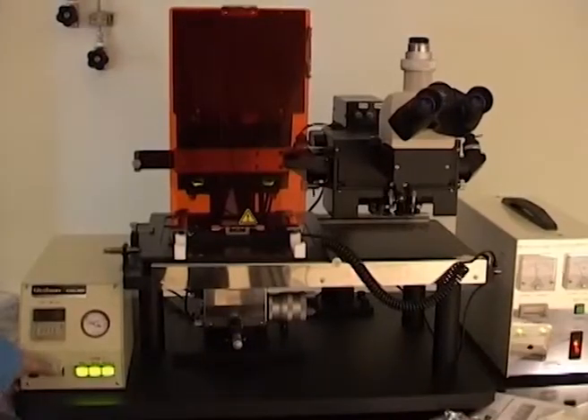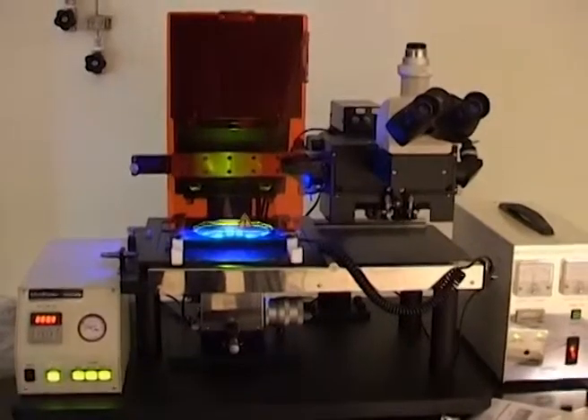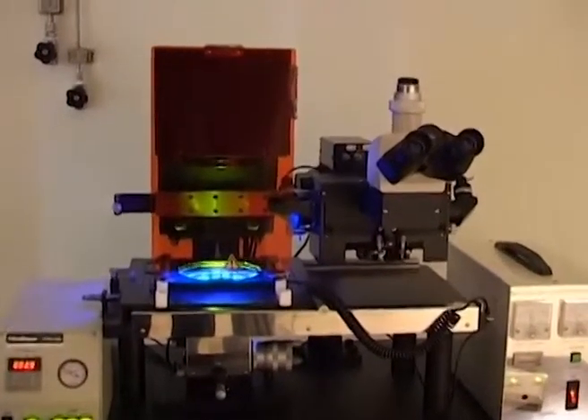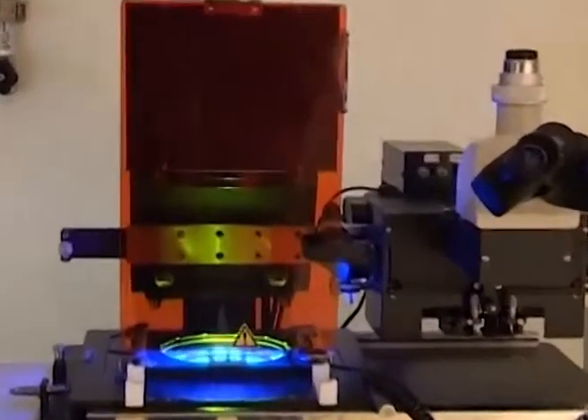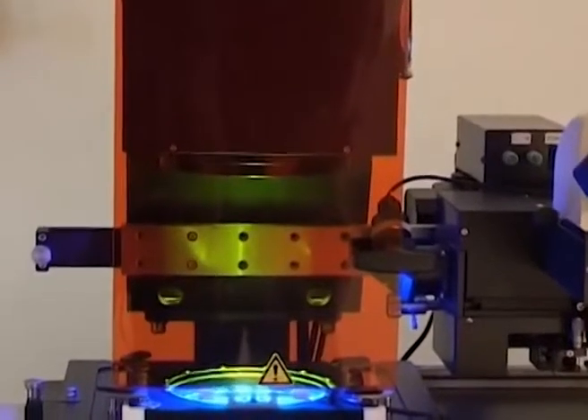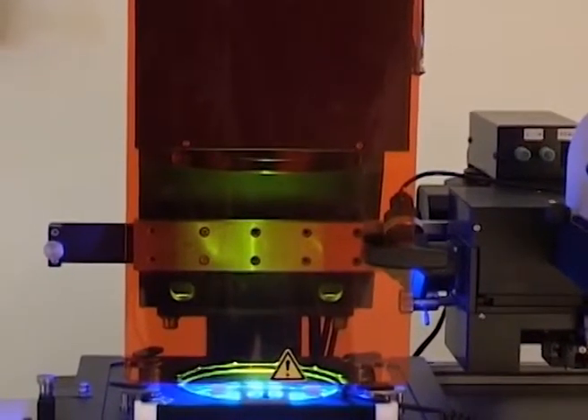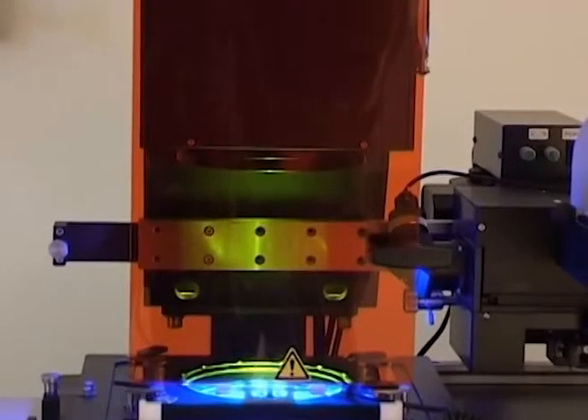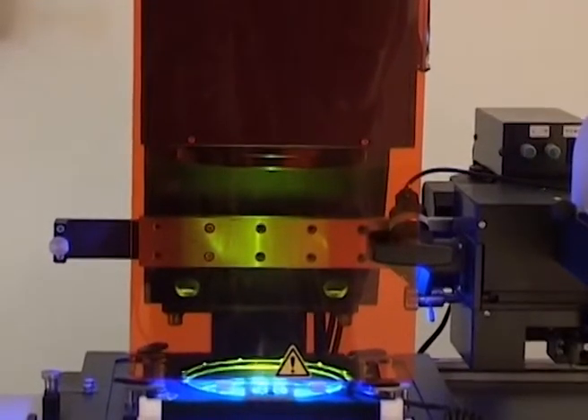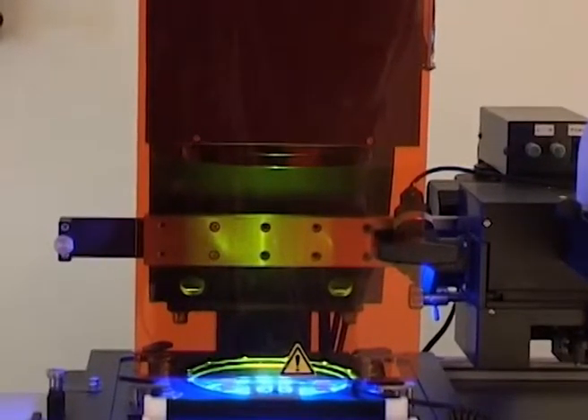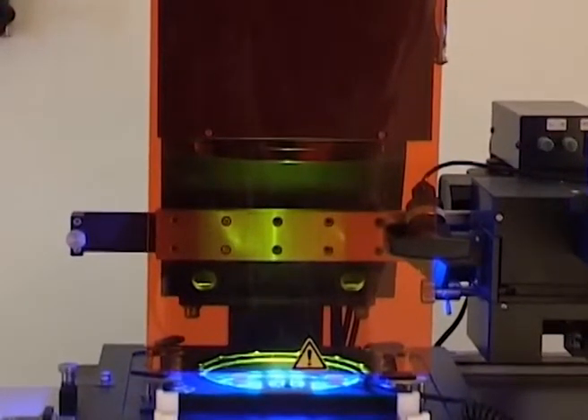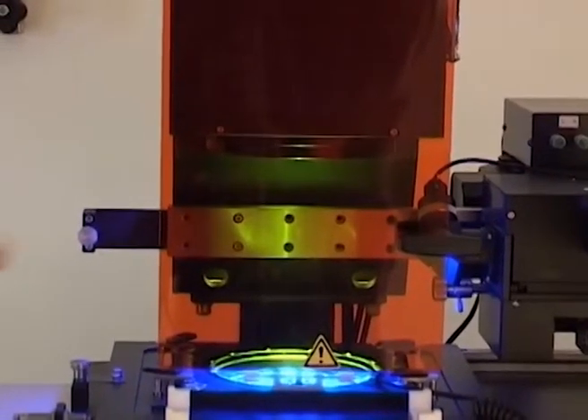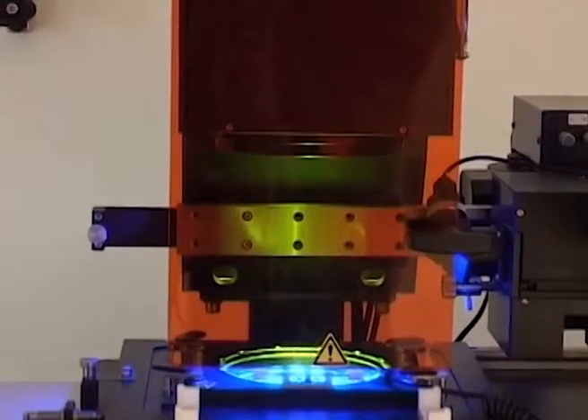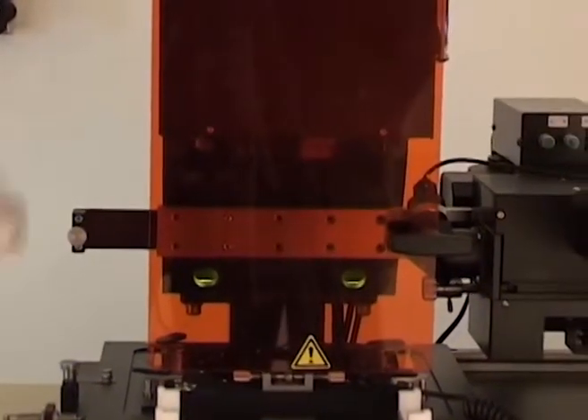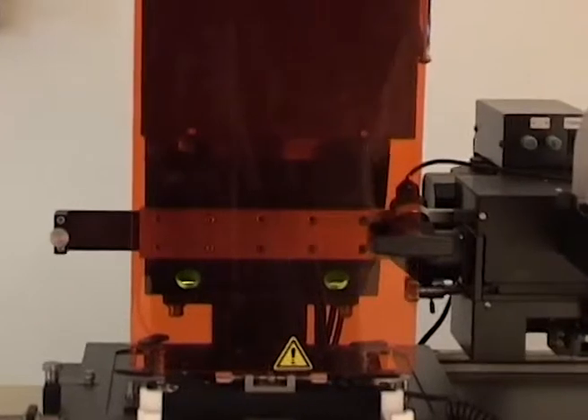So I'm going to now turn on the exposure light, and as you see here, the moment I turn it on, the timer clock has started, and the UV light is now falling sharply onto the wafer. The time reading here is rapidly reaching the 22 second mark that we had set before. And the moment that is done, the exposure light will go off, and our exposure process of the photoresist is complete. As a matter of fact, it is just complete now.